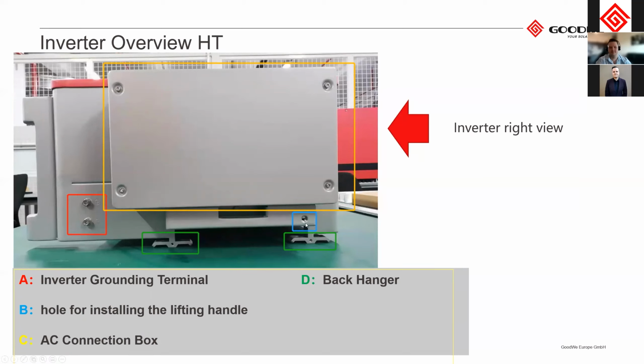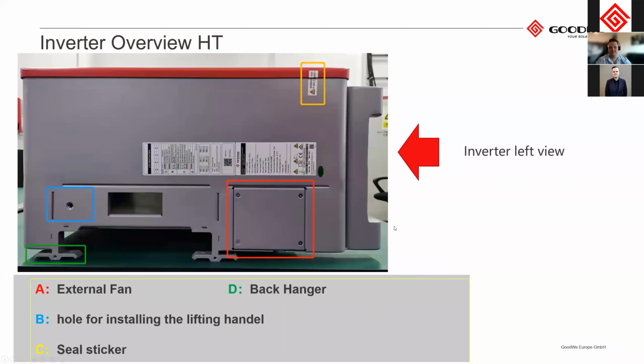So if the devices are slightly heavy, I'll show that in the installation overview. We do have places where you can install hanger bolts to lift the device up. And then we have the other side view, where you can see the other hanger bolt and the external fan connector. This one has 4 screws, and then you can slide out the whole fan assembly for the device. So this is for maintenance.